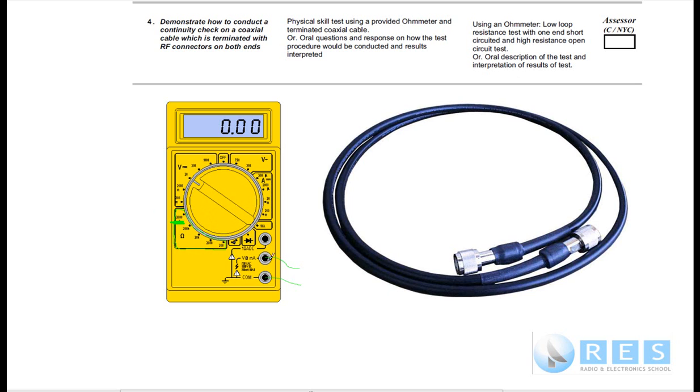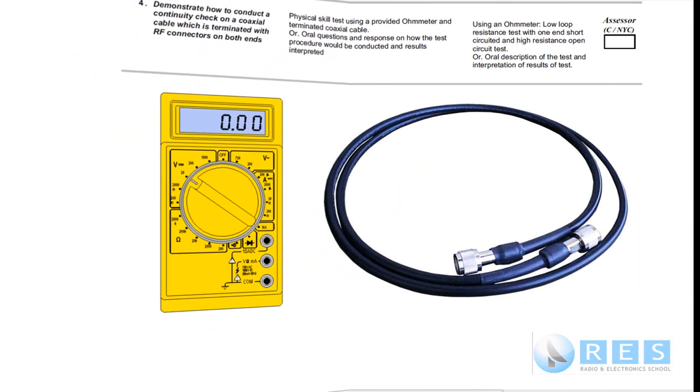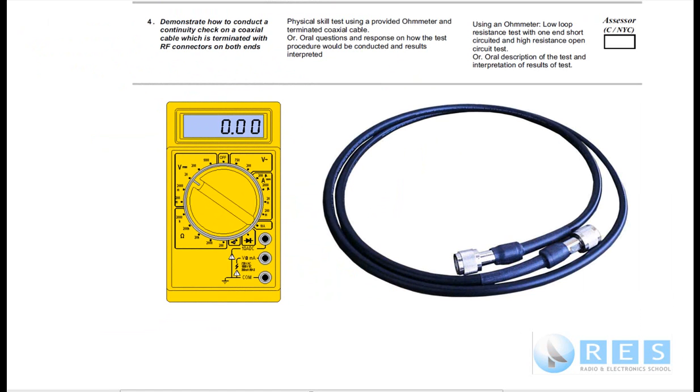You would switch to the high ohms range and put the multimeter, one lead on the pin and the other lead onto the outside. Since the other end of the plug should be open circuit and the center conductor should not be touching the outer shield, you would read a high resistance or infinite resistance. On the high ohms scale going between the center conductor and the outer conductor with the other end open, you should read a very high resistance or an open circuit. So we've checked for a high resistance on one end between the pin and the shield.